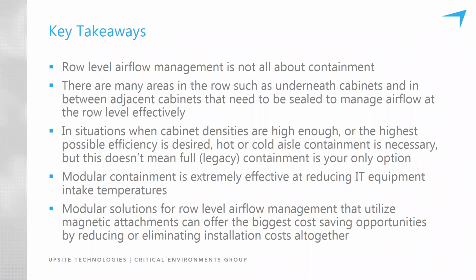Yeah, so it's important to understand how rigidly enforced your local jurisdiction is with where your data center is located, right? So municipalities might have some rules that you need to be aware of. Your facility may have insurance requirements from your carrier that you may need to be aware of as well. So those are all important considerations, and the containment providers are absolutely aware of that, right? So like for doors or a capped aisle, you don't want to prevent, or really in any scenario, you don't want to prevent the fire suppression from getting access into that aisle if that's where it needs to be, right?